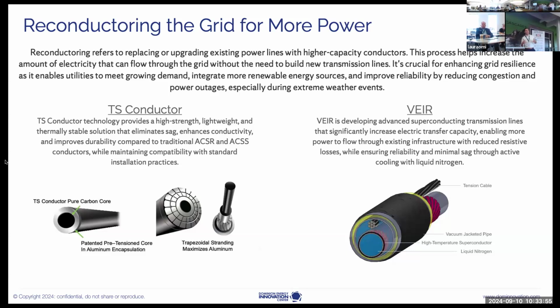Look around you at all the big towers, your 100, 120, 500, 750 kilovolt lines, the ones that look like they have arms. Those are moving electrons over aluminum. The bulk of our transmission system is aluminum conductored lines around what has historically been a steel core. You need the strength of steel for tension across your towers, but you need aluminum for conductivity. Would copper be better? Sure. Is copper ridiculously expensive? Absolutely. So you go with the next best thing, high purity aluminum.